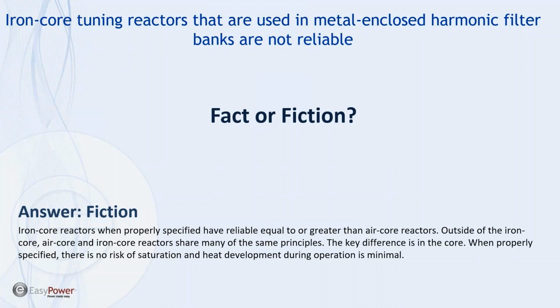If I have a reactor that's rated 100 amps of the fundamental, in other words, it has a reactive power rating equal to 100 amps, we would design and request the reactor supplier for a reactor that had a rating of either 135 or 150. And what that does is it forces the reactor supplier to put iron into the design and to basically design in reliability.